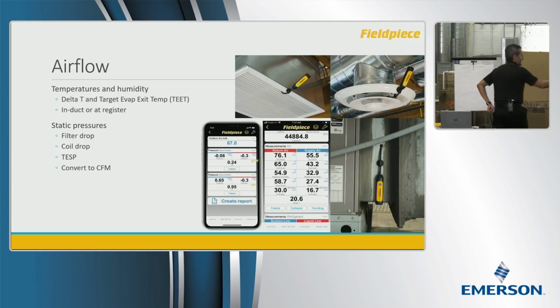Now, the fact that I can see both P1 and P2, I can see, well, on the return side, I'm at 0.65. It's kind of high. On the supply side, 0.3, that's not too bad. So I know now, as a technician, I probably am not going to use too much time searching for issues on the supply side, but I'm going to focus my efforts on the return side. So being able to see individually what the pressures are on both sides will help you as a technician save time by focusing your efforts in the areas where you're going to find the restrictions. So it's very, very useful to be able to see that differentiation. And it makes your job a little bit easier too, you don't have to play with a bunch of really long 6-foot hoses, and hopefully you can get them right to where they're supposed to go. You could have short hoses that come with static pressure probes, insert directly into the duct. Now, going back to accurate readings.